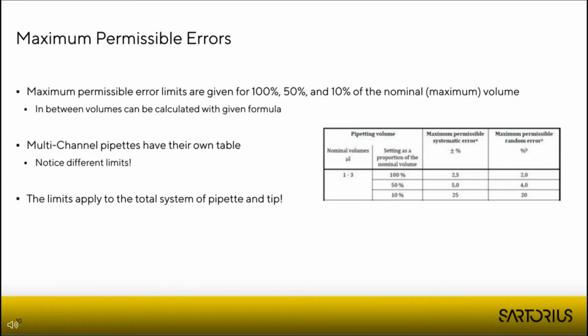Then the maximum permissible errors. Even the first revision had some maximum permissible errors, but in the second revision, they made it easier for the end user. This is my view on that. In the first edition, they only gave you error limits for the nominal volume of the pipette. Let's take a case example, a 100 microliter volume pipette. They would only give you limits for 100 microliters, and then you needed to calculate yourself, based on the microliter value, the percentage maximum error for the adjusted volume. So if you use the 100 microliter pipette at 50 microliters, you needed to use the same microliter maximum permissible errors and calculate the percentage based on that.